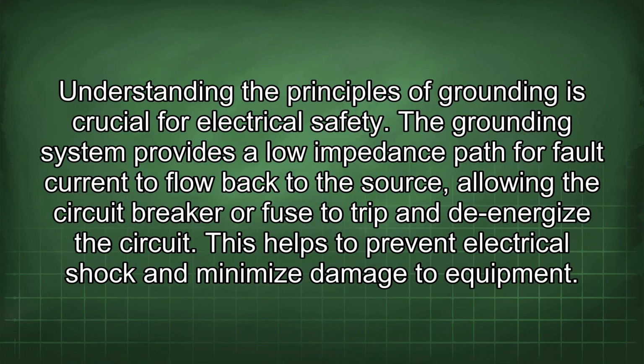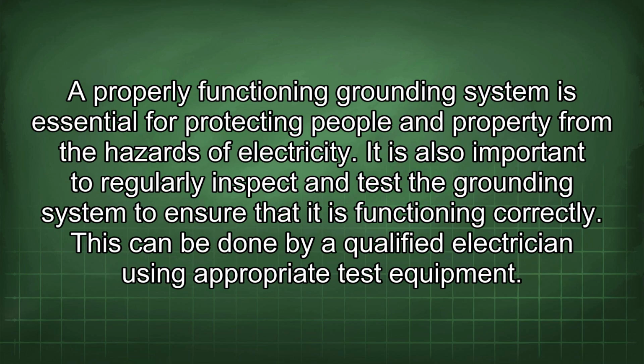Understanding the principles of grounding is crucial for electrical safety. The grounding system provides a low impedance path for fault current to flow back to the source, allowing the circuit breaker or fuse to trip and de-energize the circuit. This helps to prevent electrical shock and minimize damage to equipment. A properly functioning grounding system is essential for protecting people and property from the hazards of electricity. It is also important to regularly inspect and test the grounding system to ensure that it is functioning correctly.